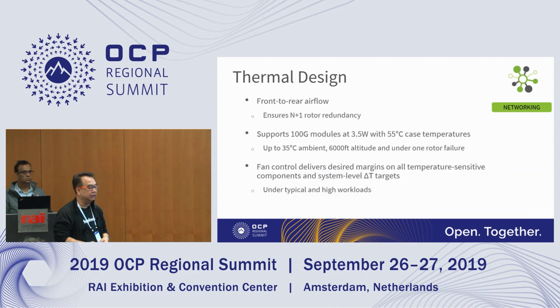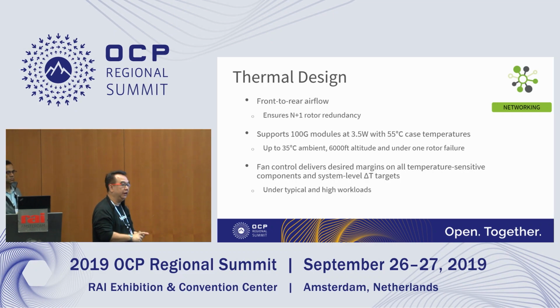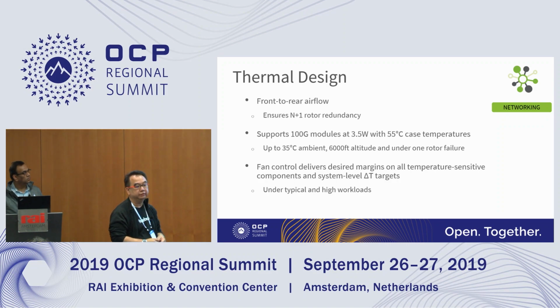For the thermal design, this is front-to-rear airflow cooling, as you can see, and for the fans it's N+1 redundancy. Because of that, we can cool 100 gig modules using up to 3.5 watts each at a 55C case temperature for those optical modules. It allows up to 35C ambient and 6,000 feet altitude, with worst case considered under a single fan rotor failure.